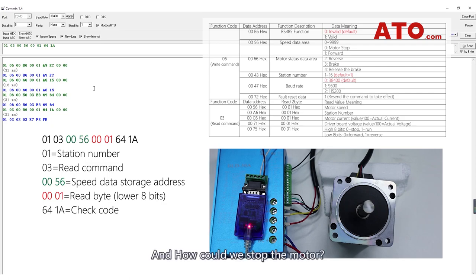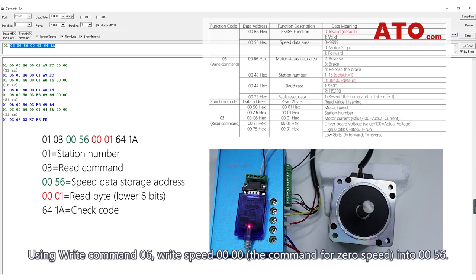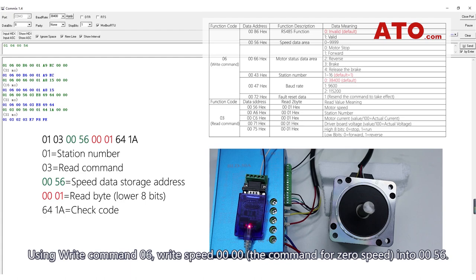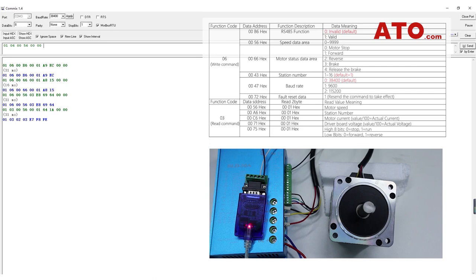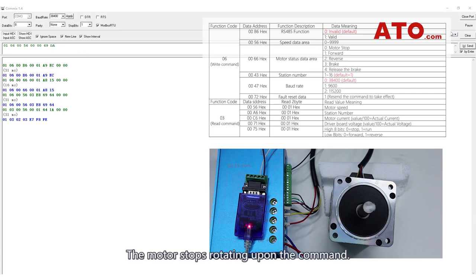And how could we stop the motor? Using write command 06, write speed 0000, the command for zero speed, into address 0056. The motor stops rotating upon the command.